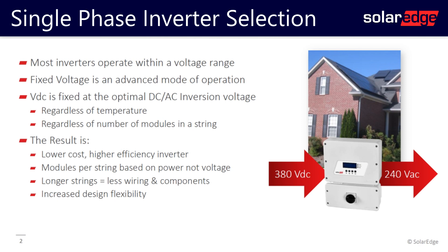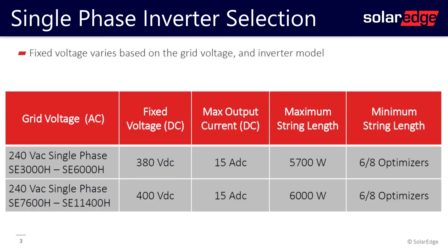What are those fixed string voltage values? For the SE3000H, SE3800H, SE5000H, and SE6000H, the fixed voltage is 380 volts DC, yielding a maximum string length of 5,700 watts. For the SE7600H, SE10000H, and SE11400H, the fixed voltage is 400 volts DC, yielding a maximum string length of 6,000 watts.